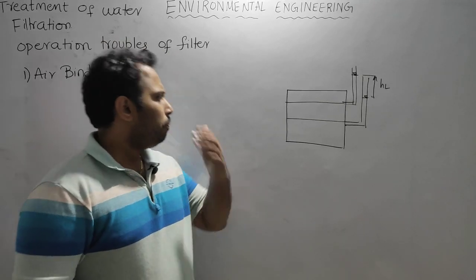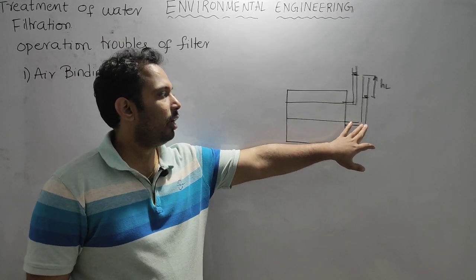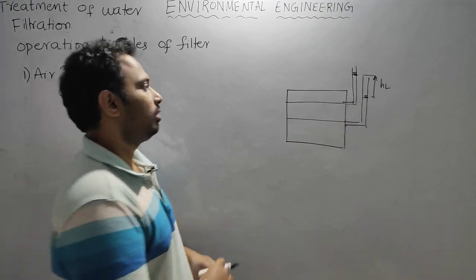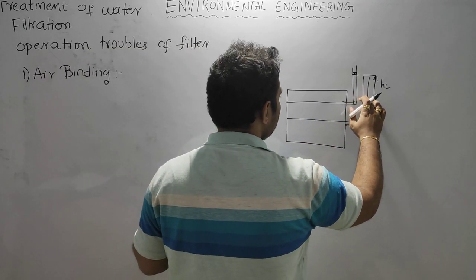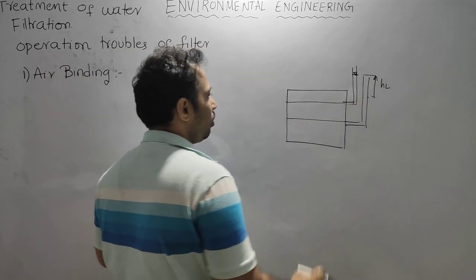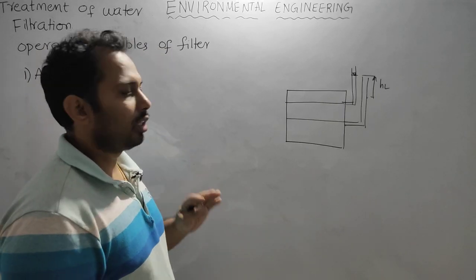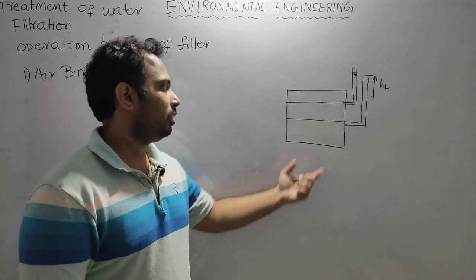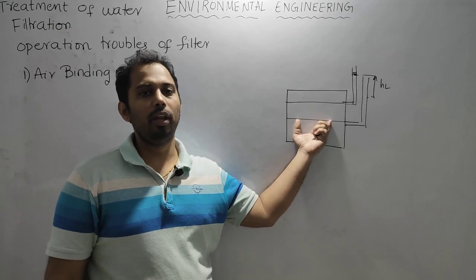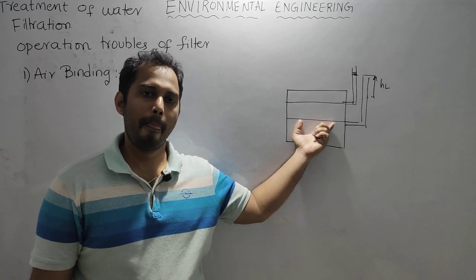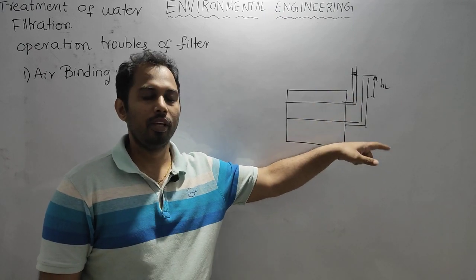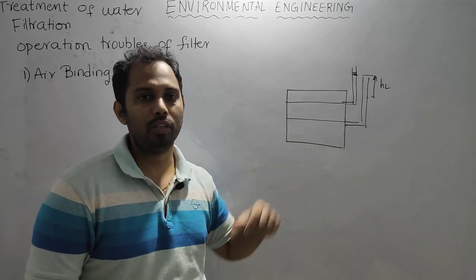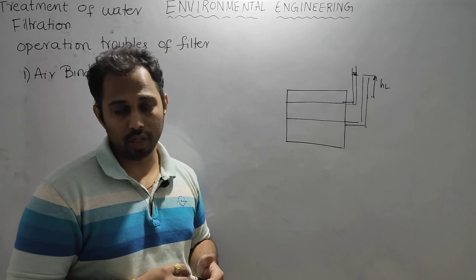When the water coming out of the filter has completely stopped, so no water is coming out of the filter now, because the filter is completely clogged, though you are sending water from the top. Then what happens in the bottom layers? A negative pressure will develop. There is no water on one side, on the other side you are loading it with fresh water, so high pressure on one zone, low pressure on another zone, which causes negative pressure to develop.